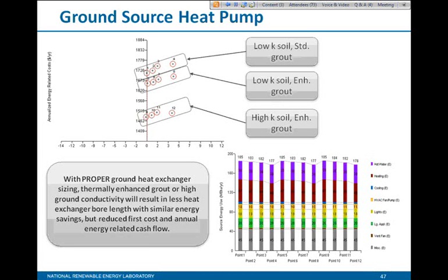With that iteration that you are talking about, it's going to consume a lot of runtime. So what we did is a simplified approach when accounting for the annual load imbalance. We define a chilled water design temperature as well as a heating water design temperature based on the peak design conditions that vary with individual climate. When we did the sizing criteria, we referred to GLHEPro as well as LoopLink.